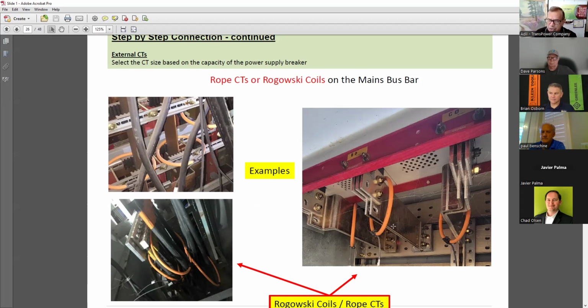Many times you don't need to shut the power down, because if you open a panel at the bottom, if it is coming from the ground, or if the cables are coming from the roof or the ceiling, you can actually catch all these cables, which are already insulated and already protected, and you can put this in live. So you really don't need a power shutdown, in many cases, if you are able to catch it without going into the part where you have exposed terminations.